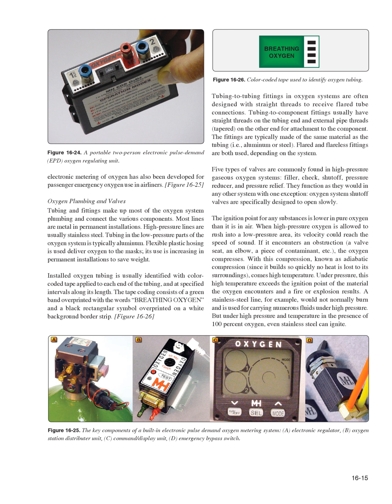With this compression, known as adiabatic compression, since it builds so quickly no heat is lost to its surroundings, comes high temperature. Under pressure, this high temperature exceeds the ignition point of the material the oxygen encounters and a fire or explosion results. A stainless steel line, for example, would not normally burn and is used for carrying numerous fluids under high pressure. But under high pressure and temperature in the presence of 100% oxygen, even stainless steel can ignite.